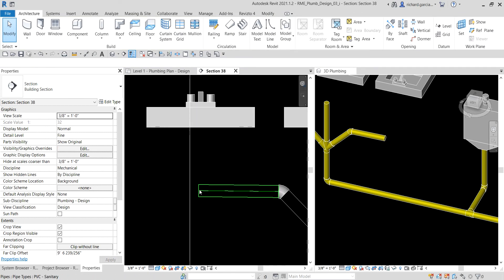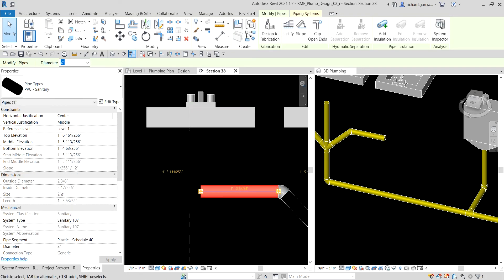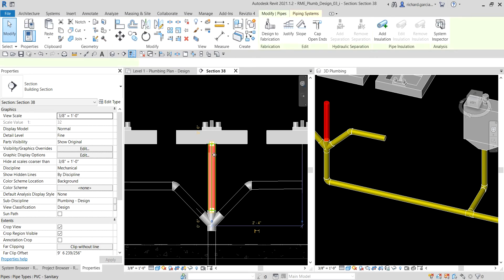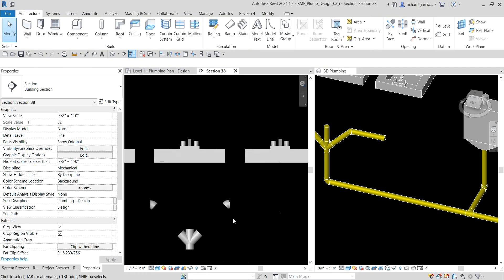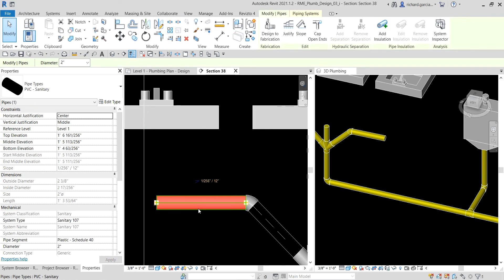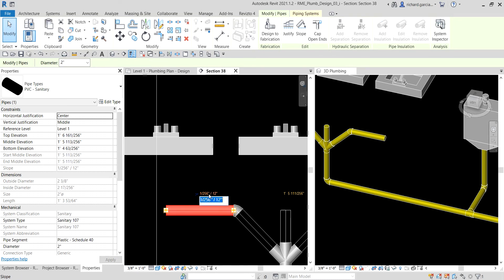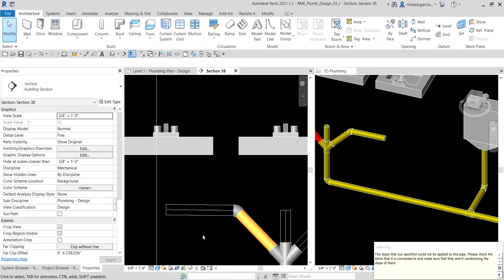The alignment icon is now appearing for the second stub, so I align it properly. I also notice this pipe segment is missing its slope, so I select it, set slope to 1/8 inch per foot, and click Finish. I close the warning dialog. Both pipe stubs now have the correct slope going toward the fitting.